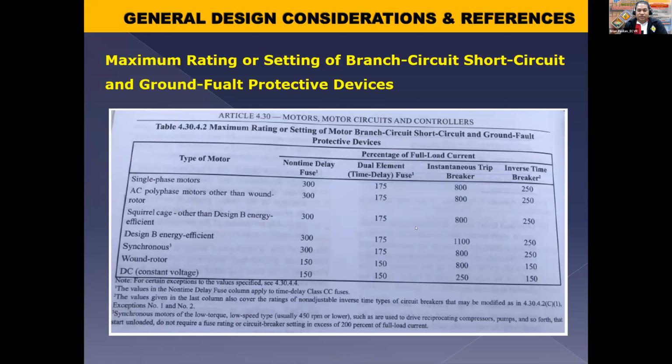Same din sa 15% of the... okay, so I would presume that ito yung combination of motor loads in one circuit ba ito, sir? No? So, ideally po, wag mong pagsabayin sila. So ang computation din is 125% of the highest motor load, or one of them kung identical, then plus the sum of other loads. Meron tayong competition mamaya, sir. Pakita ko lang mamaya yung combination of motor loads, okay? Sige, to answer fully your question po.